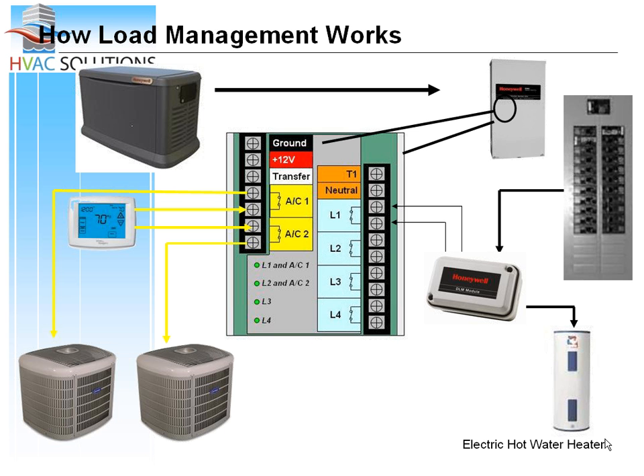So the priority is AC1 and L1, second priority is AC2 and L2, then L3 and L4. You can play with these a bit in strange circumstances—maybe that well pump needs to be first priority, so we leave it on L1. And let's say there's only one air conditioner, not two—we can then put that air conditioner on AC2 instead of AC1.